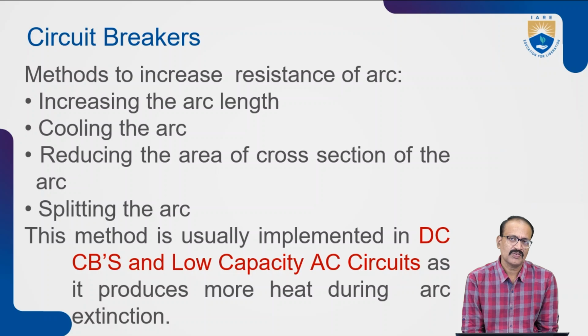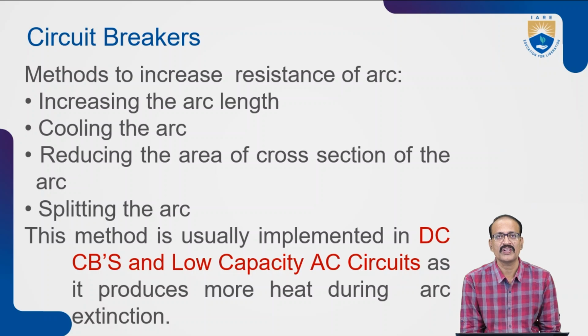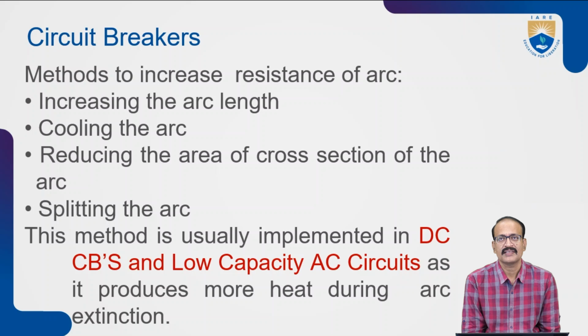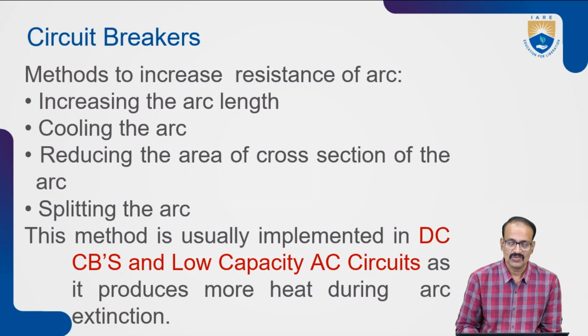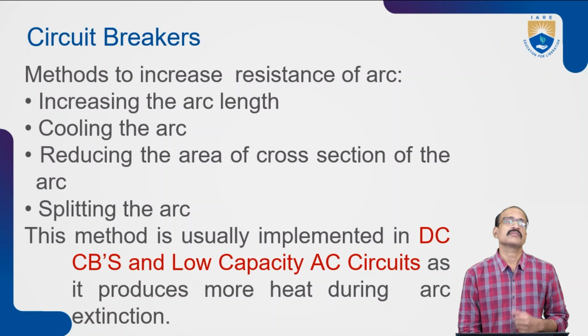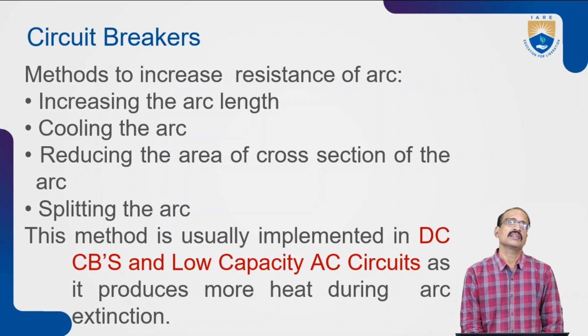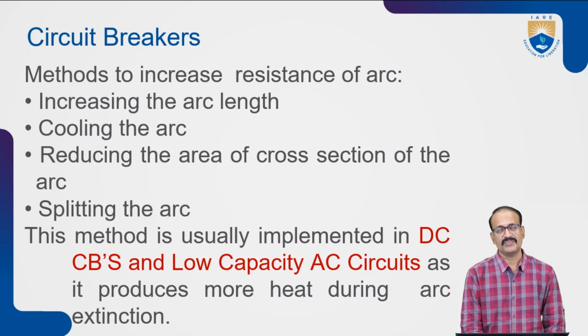So generally this method we are using in DC circuit breakers and low capacity AC circuit breakers, as it produces more heat during arc extinction. So during the arc extinction, so much amount of heat is produced. Because we are increasing the resistance, that's why we are using this type of method in DC and low capacity AC circuit breakers.